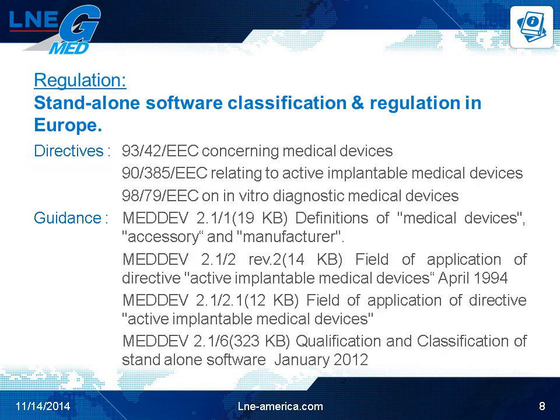During this presentation I want to review some of the applicable regulations and guidances we'll use throughout. Medical devices are regulated in Europe by three main directives: 93/42/EEC concerning medical devices, 90/385/EEC concerning active implantable medical devices, and 98/79/EC on IVDs. All of them can deal with standalone software, because software can be a medical device or an accessory in these three categories. Guidance is also available to allow a better understanding of the definitions used in the regulations, or the applicability of existing regulations — the following examples are not an exhaustive list.